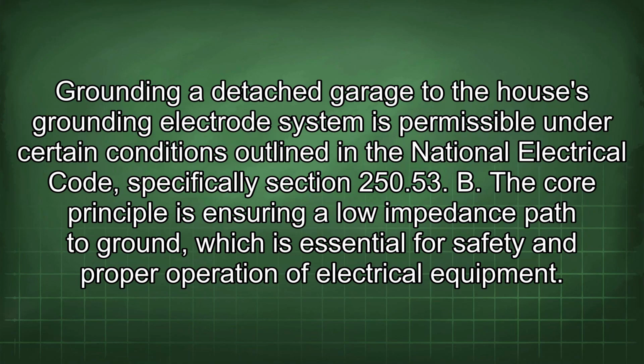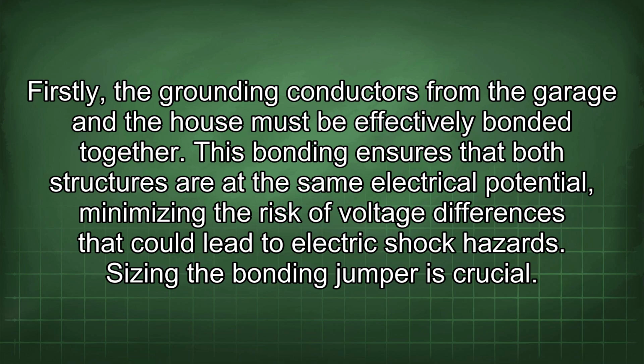Grounding a detached garage to the house's grounding electrode system is permissible under certain conditions outlined in the National Electrical Code, specifically Section 250.53(B). The core principle is ensuring a low impedance path to ground, which is essential for safety and proper operation of electrical equipment. Firstly, the grounding conductors from the garage and the house must be effectively bonded together. This bonding ensures that both structures are at the same electrical potential, minimizing the risk of voltage differences that could lead to electric shock hazards.